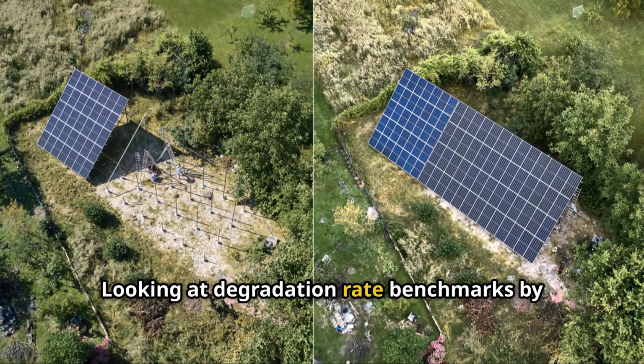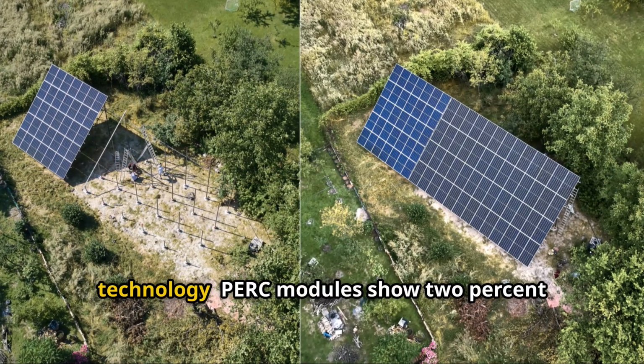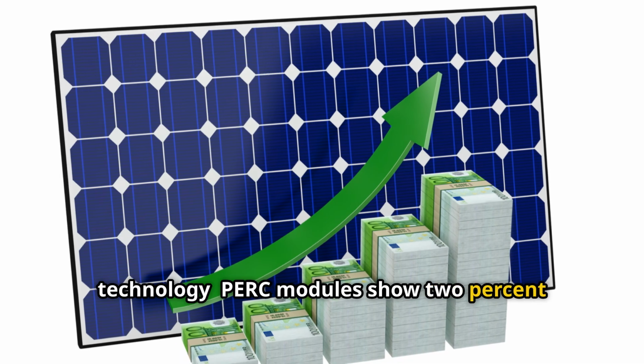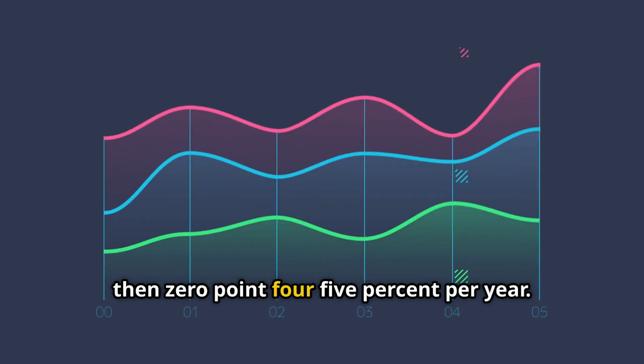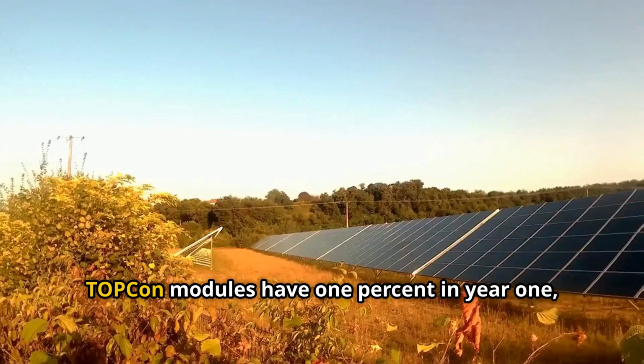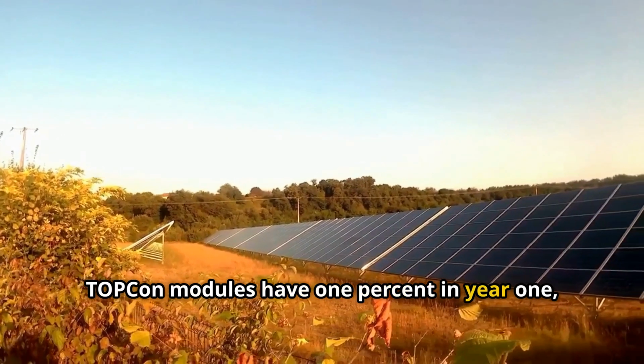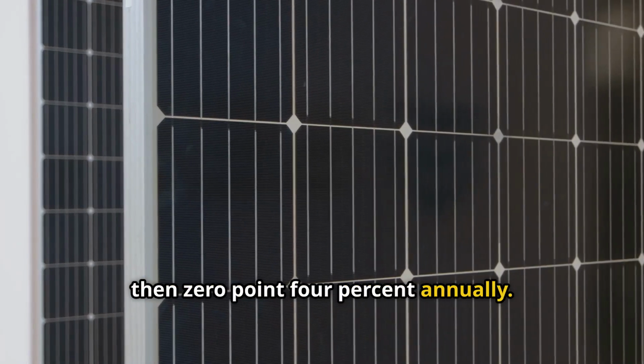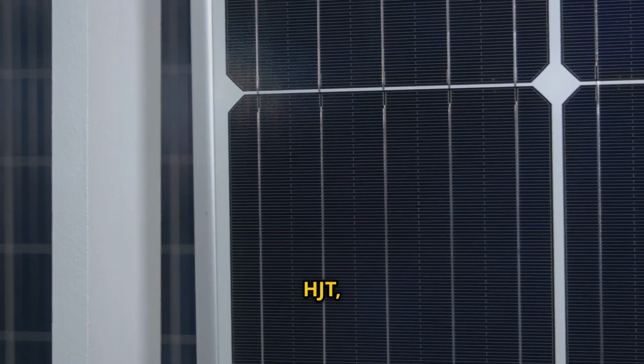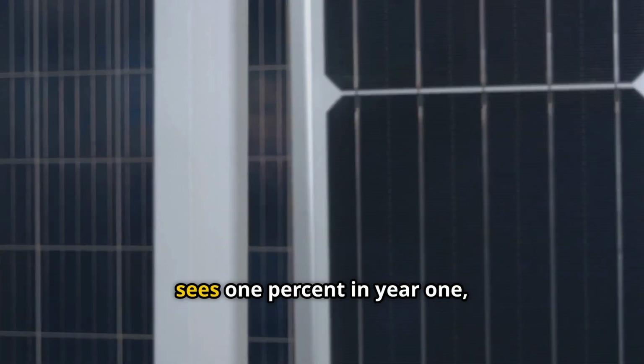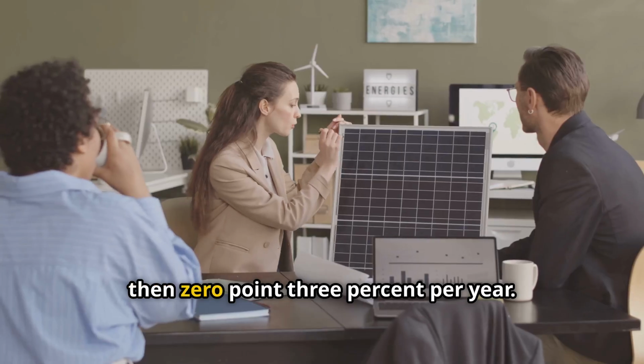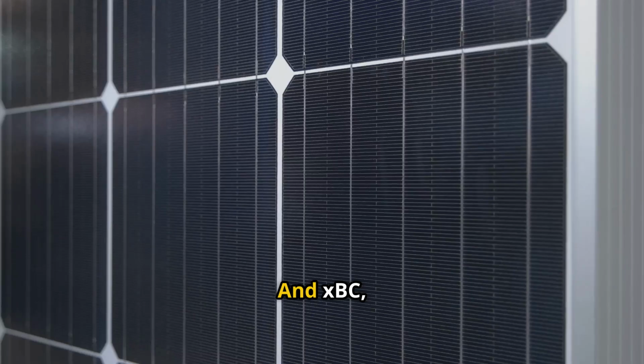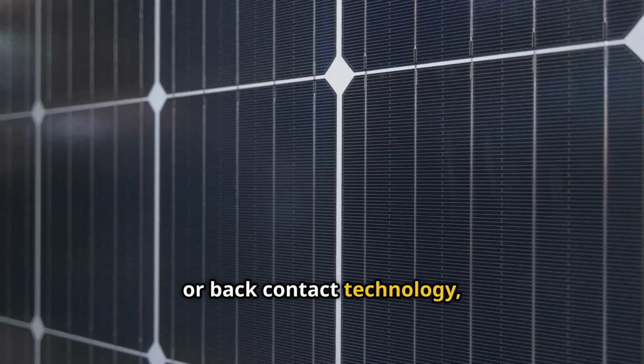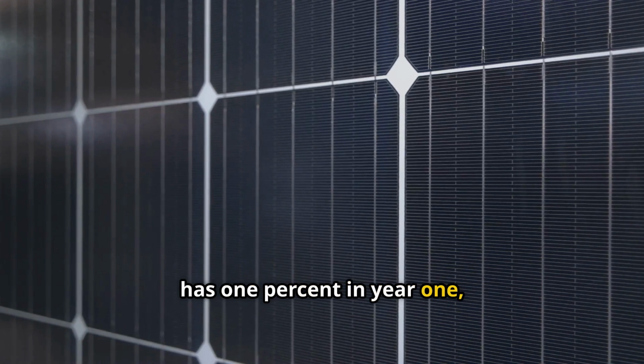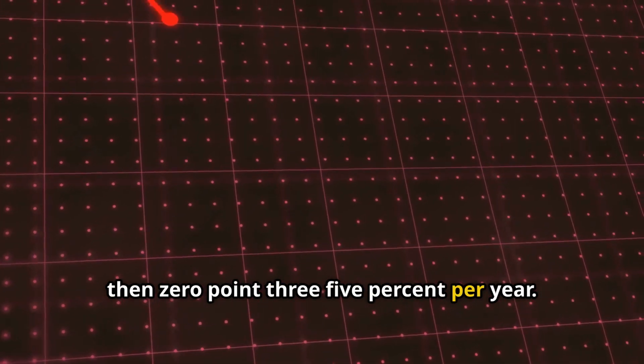Looking at degradation rate benchmarks by technology, PERC modules show 2% in year 1, then 0.45% per year. TOPCon modules have 1% in year 1, then 0.4% annually. HJT, or heterojunction technology, sees 1% in year 1, then 0.3% per year. And XBC, or back contact technology, has 1% in year 1, then 0.35% per year.